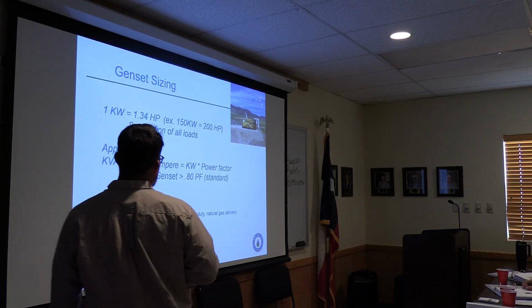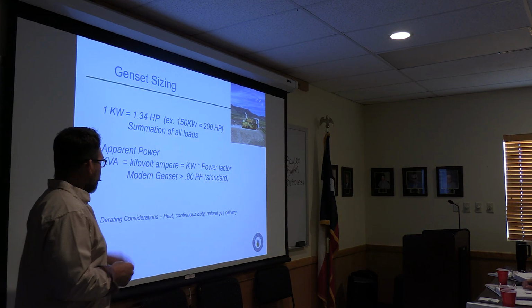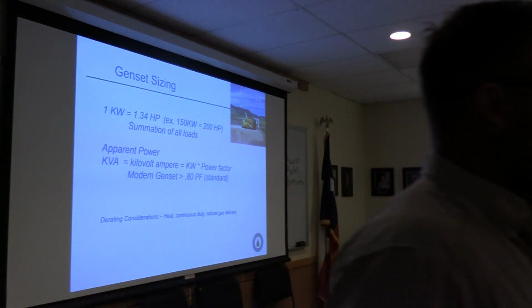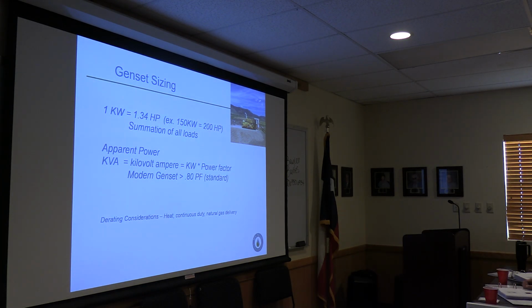Also add to it, because of where we bump and what time of year it is, you've got to use some derating considerations. If a motor is rated at 200 horsepower, that's not going to be 200 horsepower at 115 degrees in the summer, running 24/7 like you're going to run the gen set.